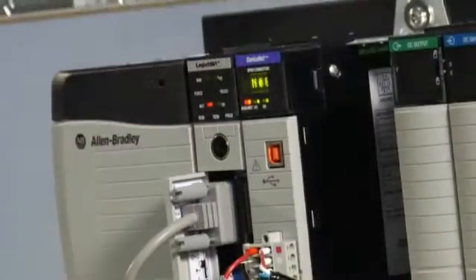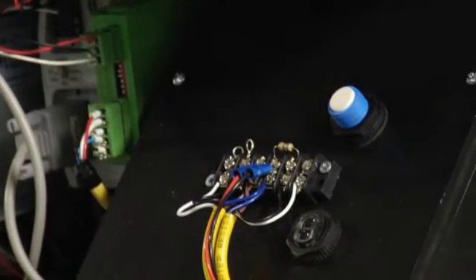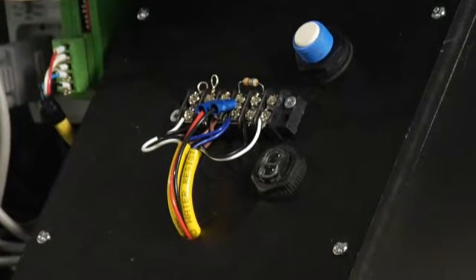Over time, internal switch contacts corrode. Arcing can cause pitting on the surface and the impedance across the contacts can change. Usually, these problems arise slowly and gradually worsen before they fail permanently.